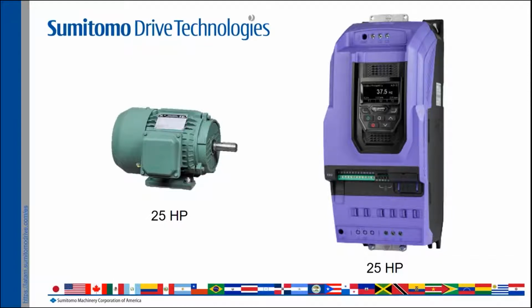So most of the people are used to say, okay, I have, for example, a 25 HP motor, so I need to select a 25 HP drive for this motor. And then most of the people say, okay, this is good, this is enough, and they tend to select like this. Of course, technically this is correct, but it is not complete.